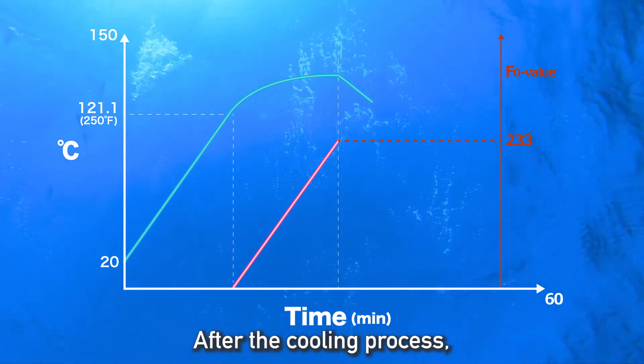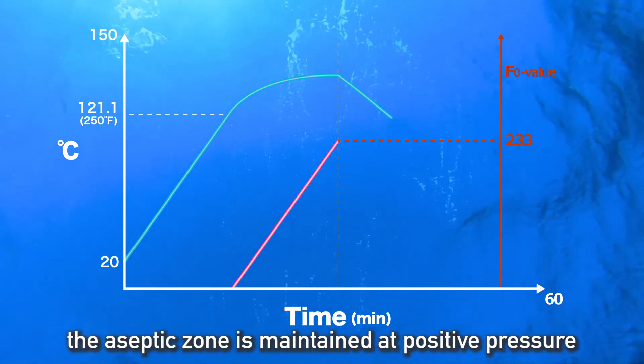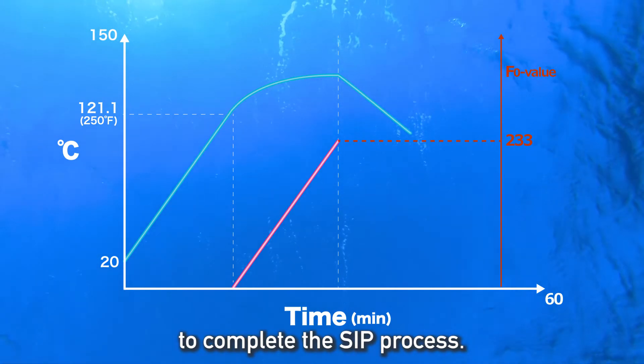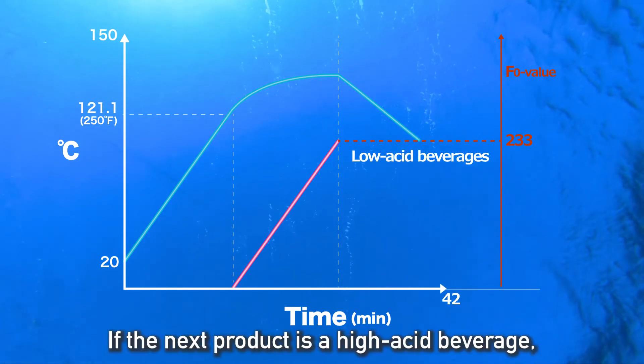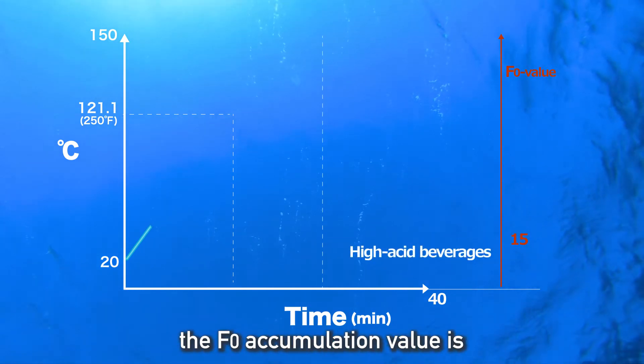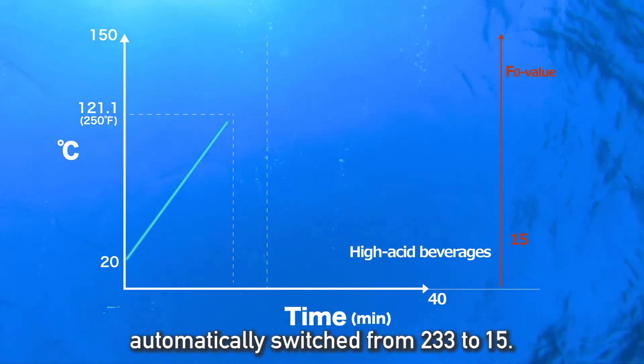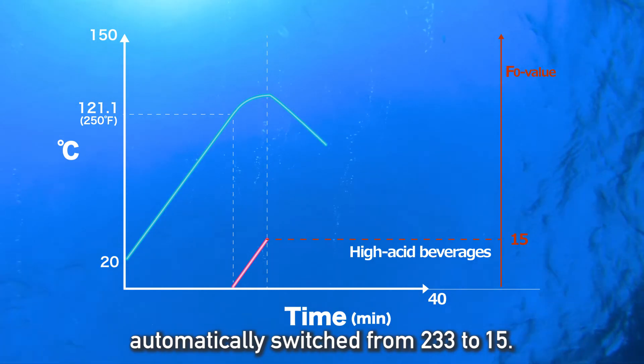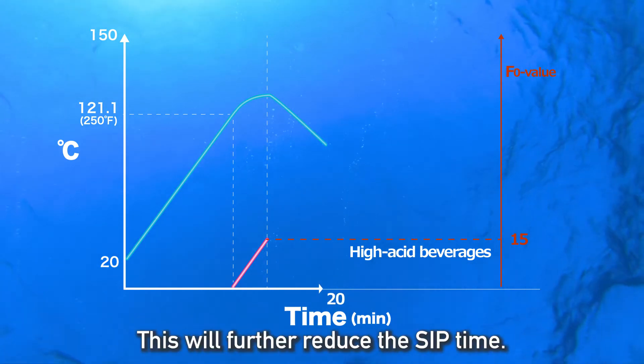After the cooling process, the aseptic zone is maintained at positive pressure to complete the SIP process. If the next product is a high acid beverage, the F-sub-O accumulation value is automatically switched from 233 to 15. This will further reduce the SIP time.